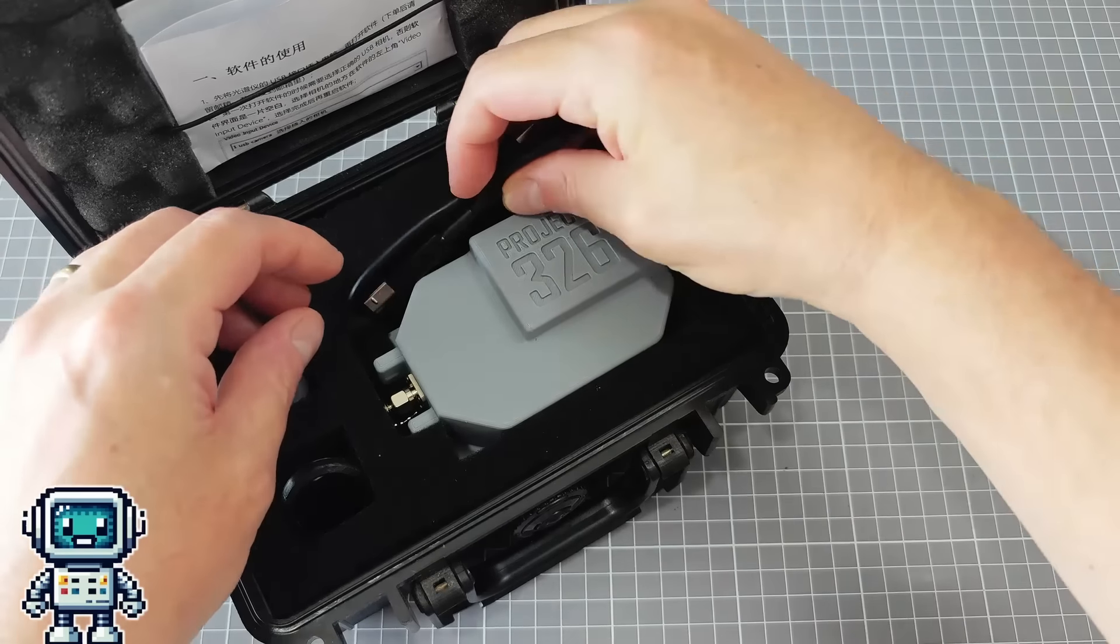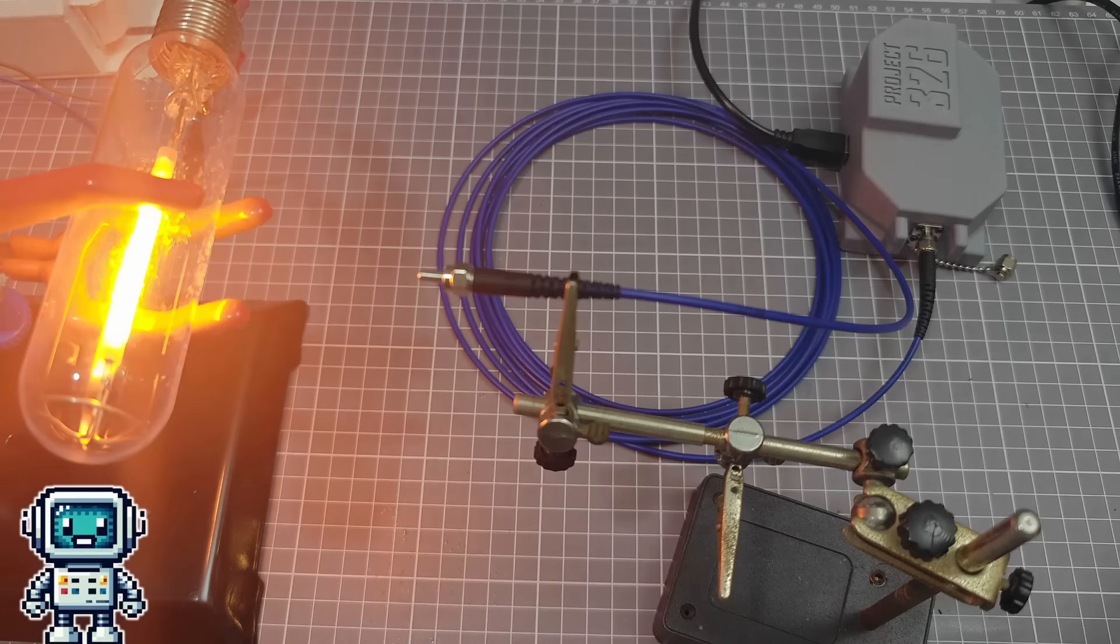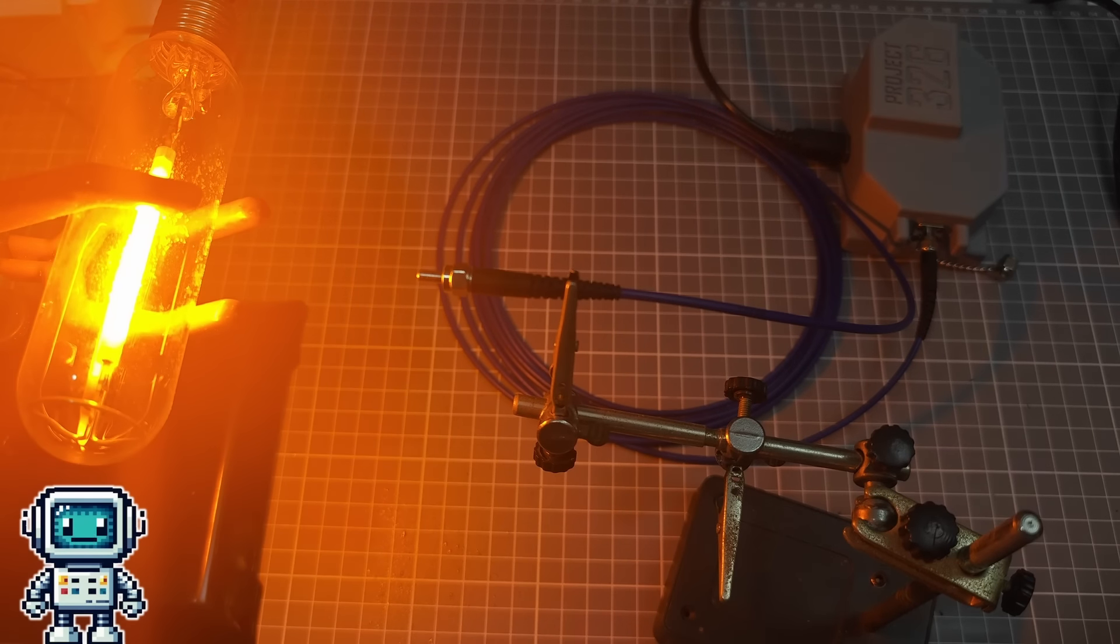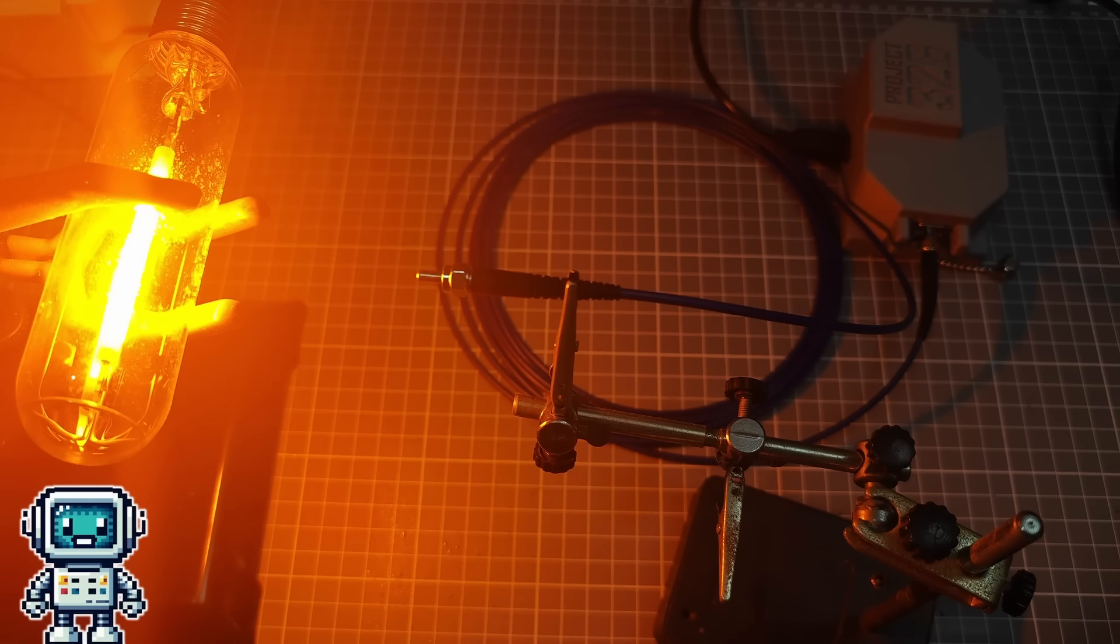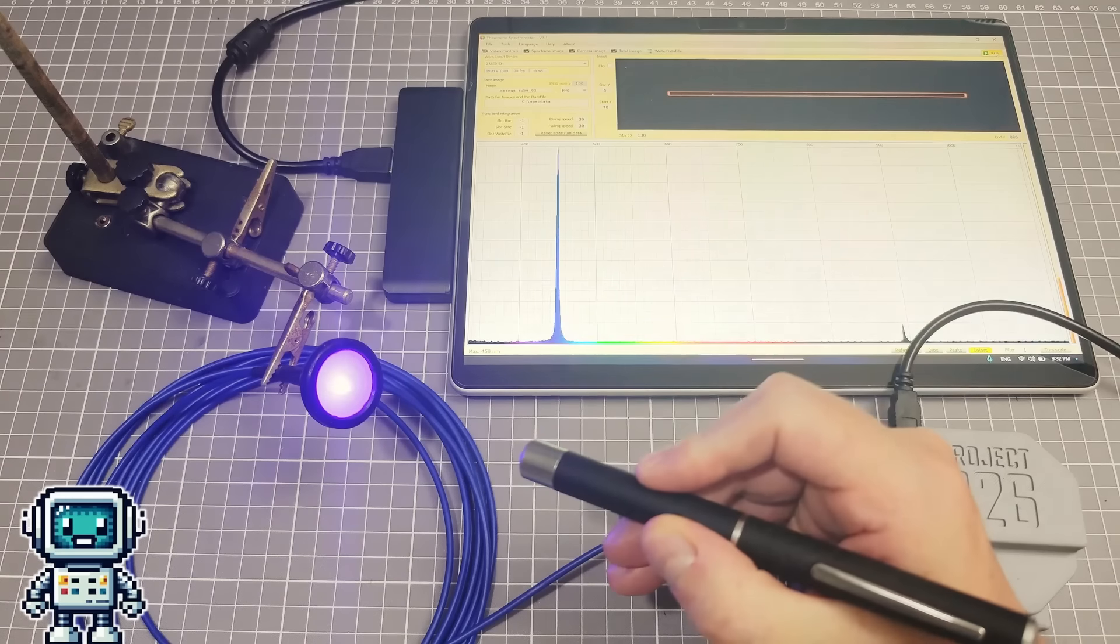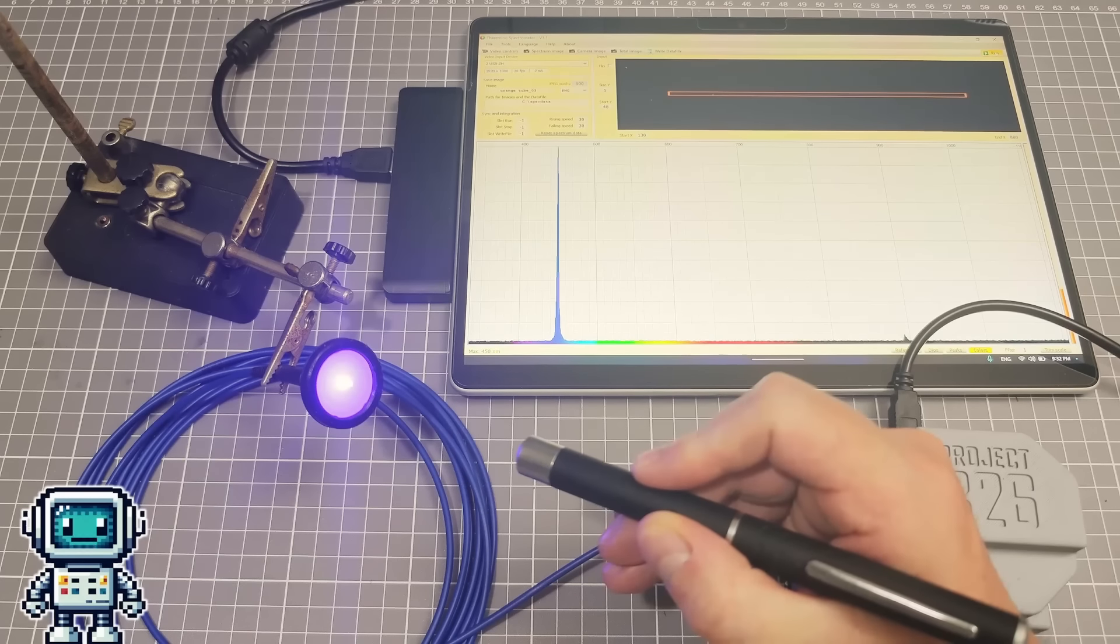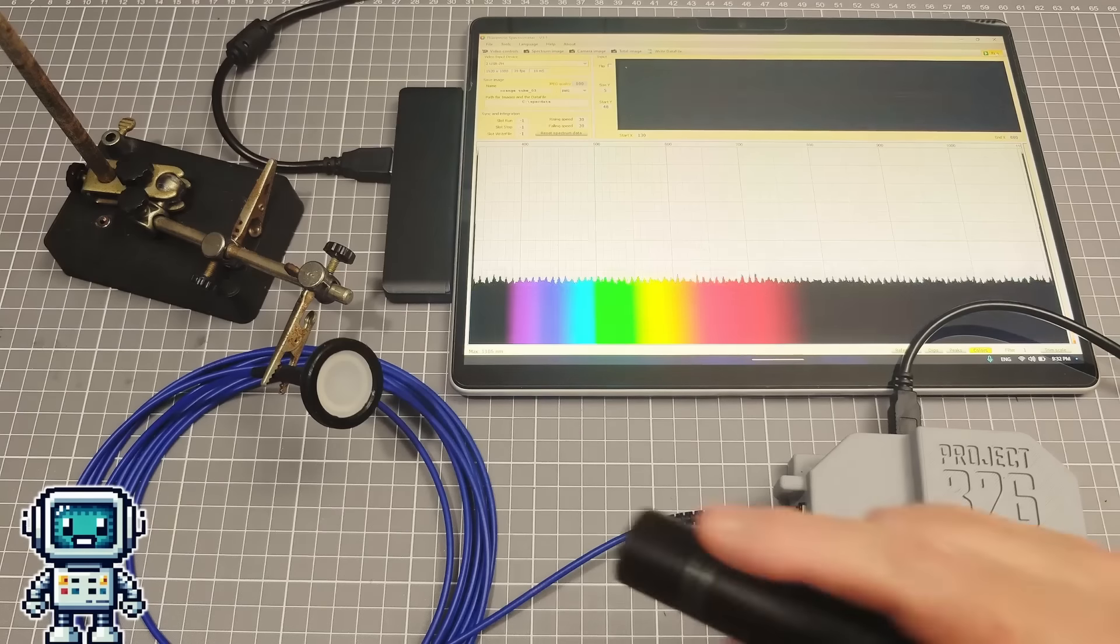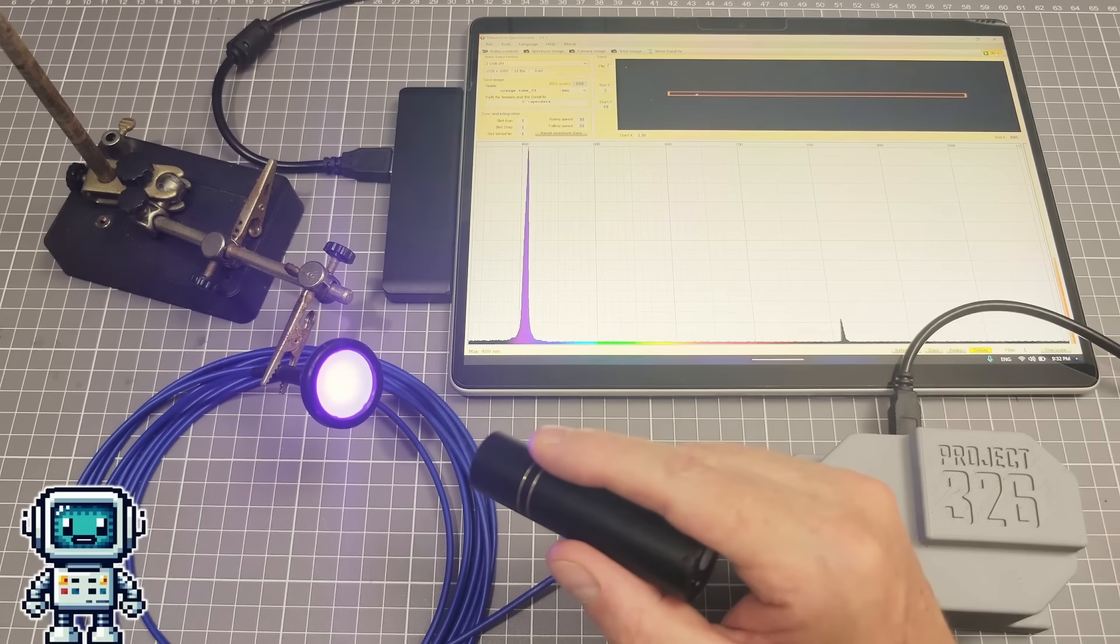The only real downside to making these changes is that the overall sensitivity of the spectrometer will be reduced, and the only risks involved are the replacement costs of a cheap spectrometer. If you are going to try and do this change for yourself, then have fun, but don't come crying to us if you screw it up. The only really irreversible change is drilling out the optical slit, which is easily replaced with the solution we have shown.